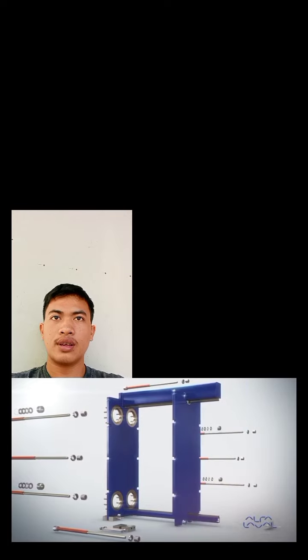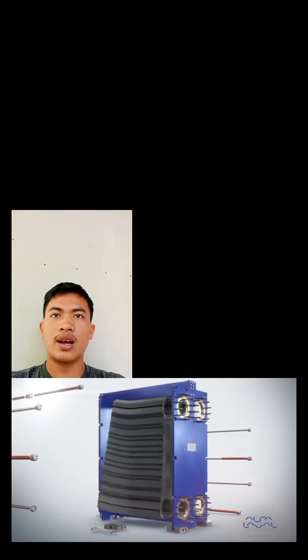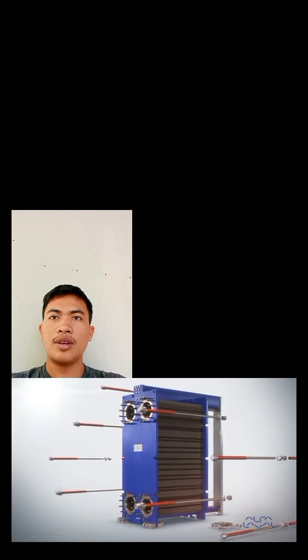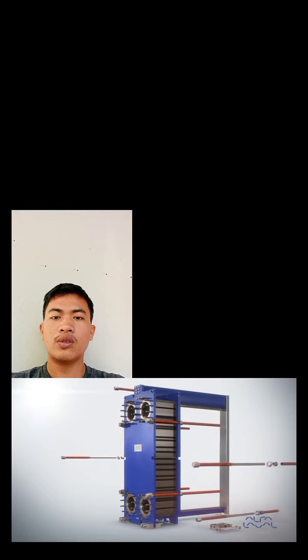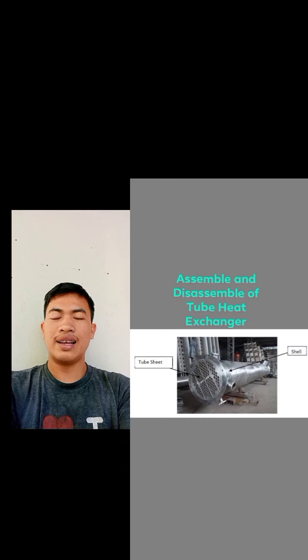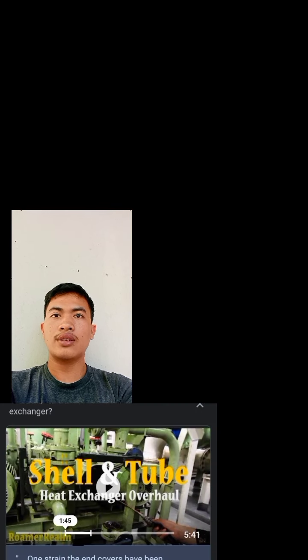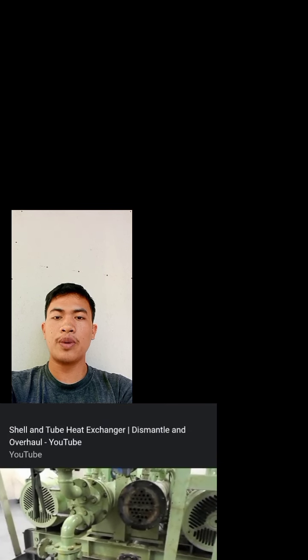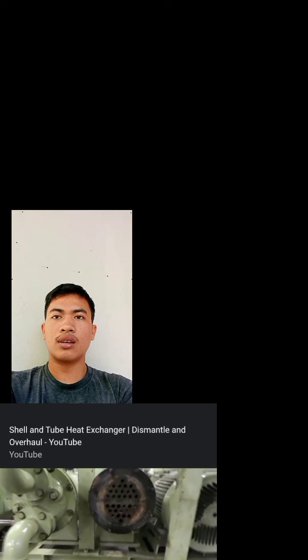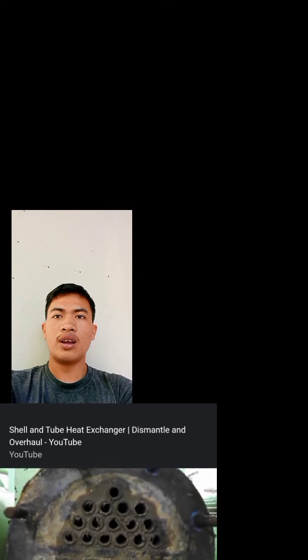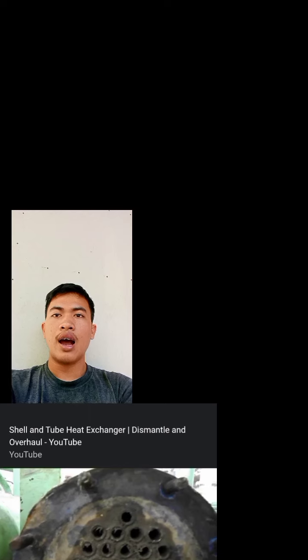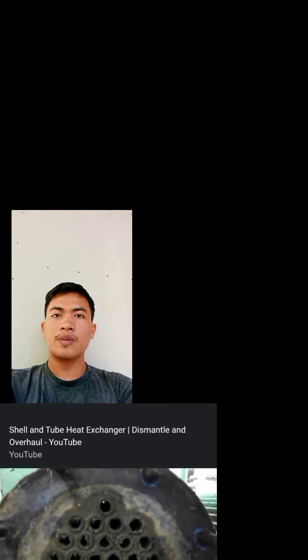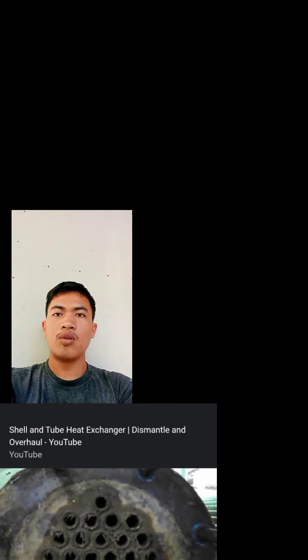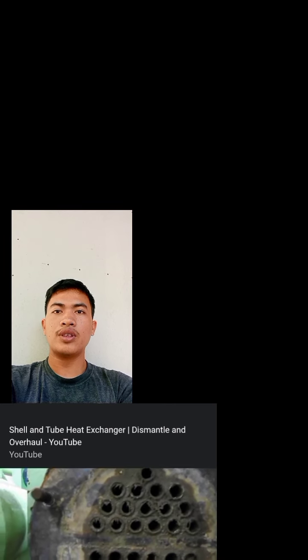Provide thermometer wells and pressure gauge pipe taps in all piping to and from the heat exchanger, located as close to the heat exchanger as possible. Assemble or install proper liquid level control and relief valve, and liquid level and temperature alarms, etc. Assemble or install gauge glasses or liquid alarms in all vapor or gas spaces to indicate any failure occurring in the condensate drain system and to prevent flooding of the heat exchanger. And assemble or install a drum upstream from the heat exchanger to guard against pulsation of fluids caused by pumps, compressors, or other equipment.